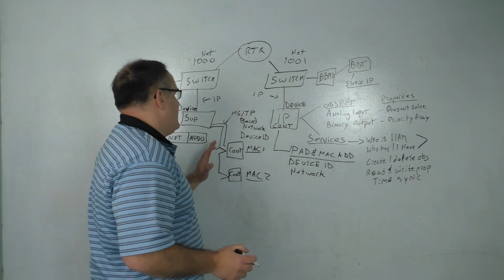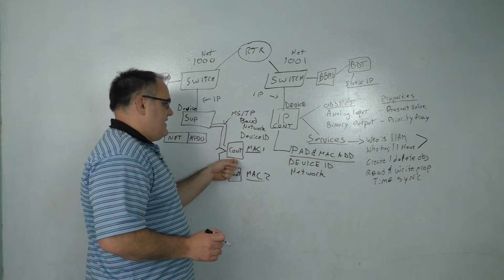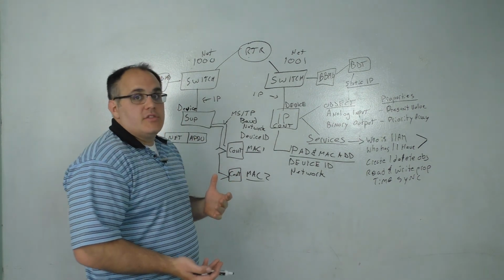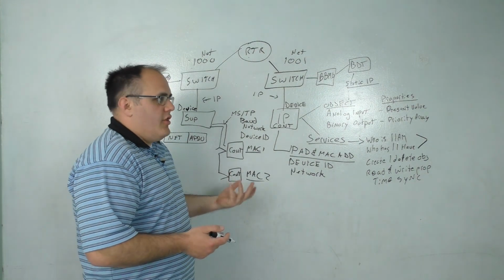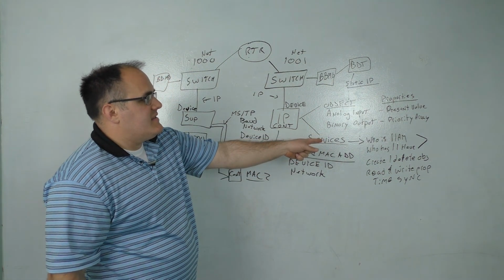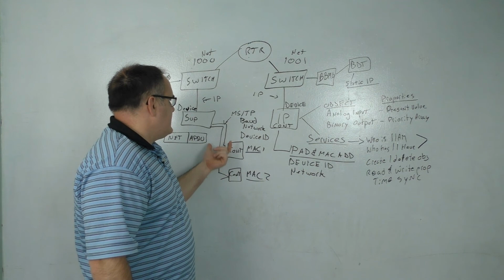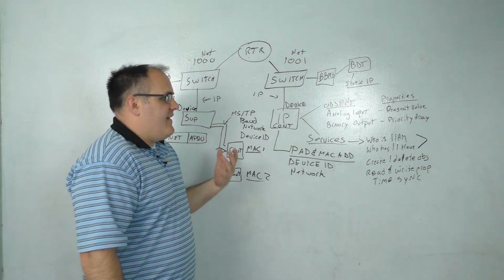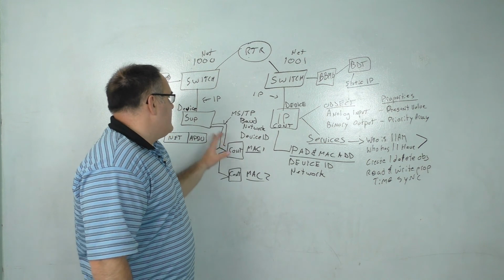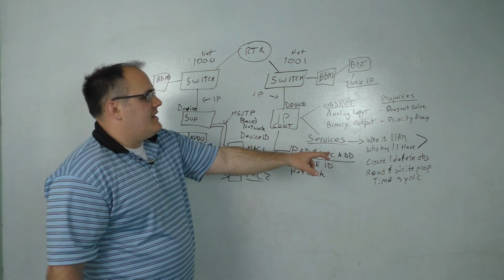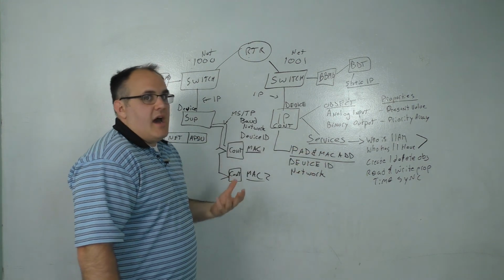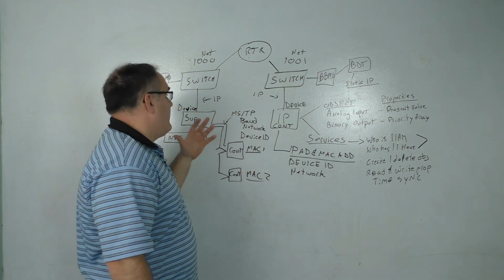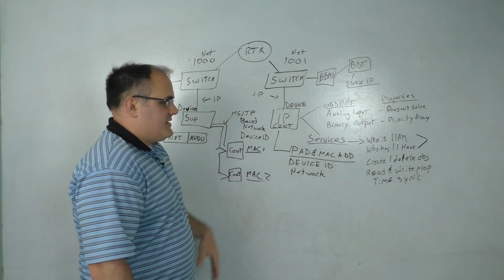So basically what's going to happen is on this network, if a BACnet device, for example, this supervisory device, wanted to go and add a new supervisory device, let's say you did a BACnet discovery. So you go on the device, you do a BACnet discovery, you're doing a who is I am, okay? So what happens is that the device will respond, I am this device, I'm of this profile, I have these objects, etc. Then what this supervisory device can do is it can go and use the create object. It can dynamically create if it supports that capability and add that device object and then add all of the objects underneath that device object to its database.